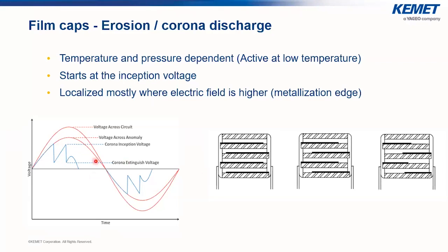Physically speaking, what happens is that we have partial discharges of this electrode, especially here on the edge, because here the electrical field is higher. So we have a kind of discharge of sparks from here to the opposite terminal. Every time we have a similar phenomenon, a portion of the metallization here evaporates. So with time, we have a decrease of the metallization length in this direction, and a decrease of the active area of the capacitor itself. From here the active area is like this; here it's reduced. If we have less active area in the capacitor, it means that we have less capacitance.